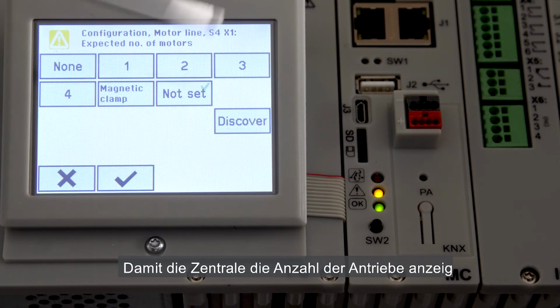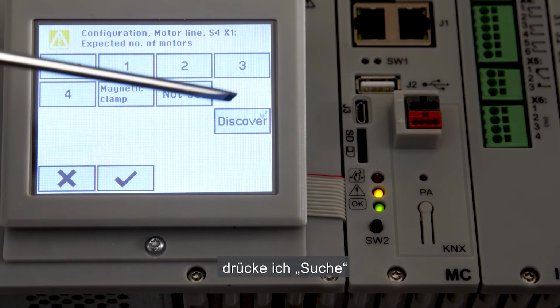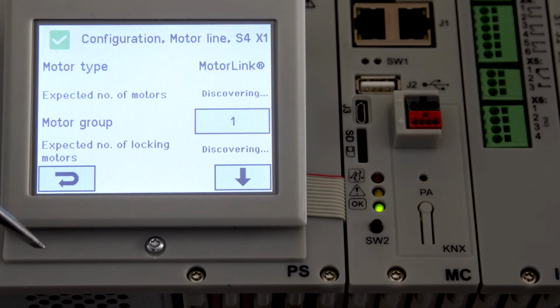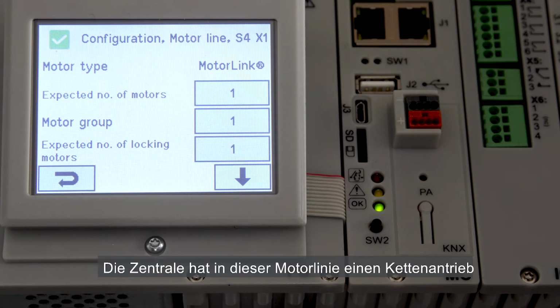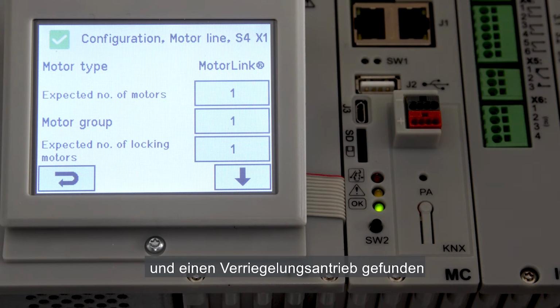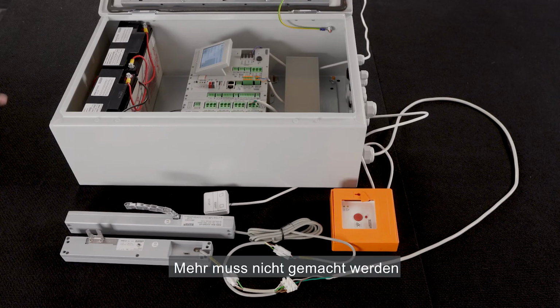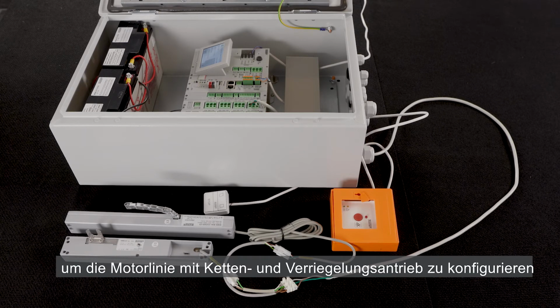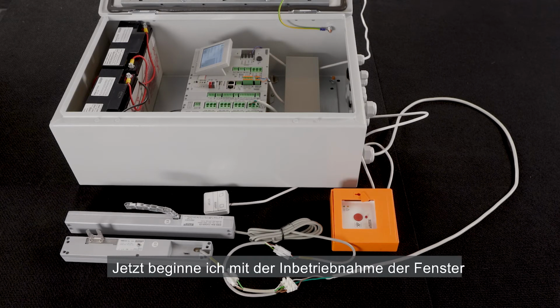I let the panel discover the number of actuators by pressing the Discover button. The panel has found one chain actuator and one locking actuator connected to this motor line. We can also see that the motor line is by default associated with the motor group 1. This is all it takes to configure the motor line with the chain and locking actuators. I'll now start to commission the window.